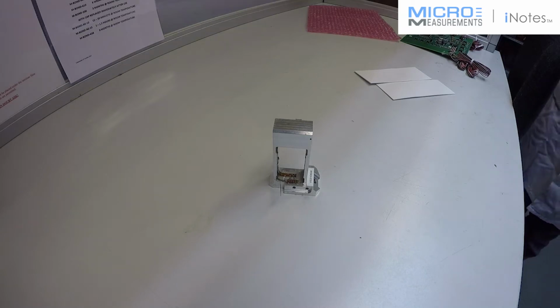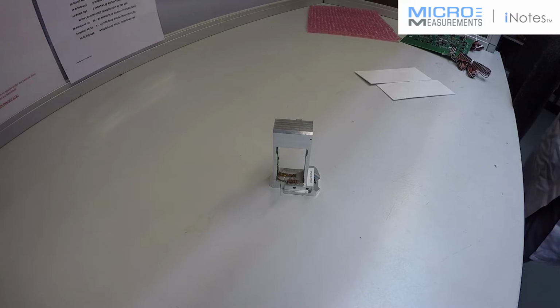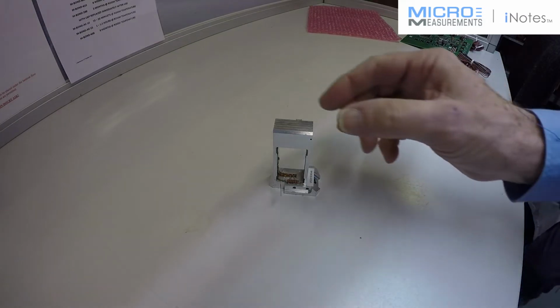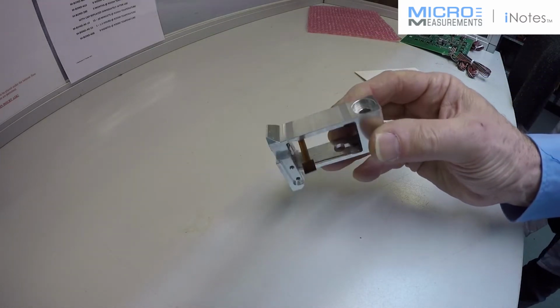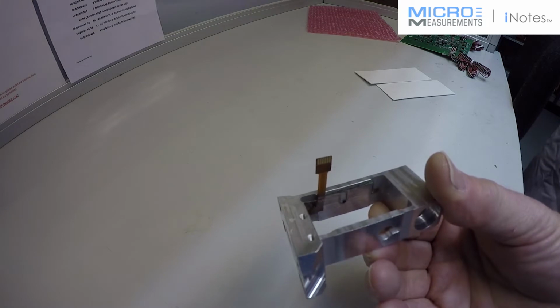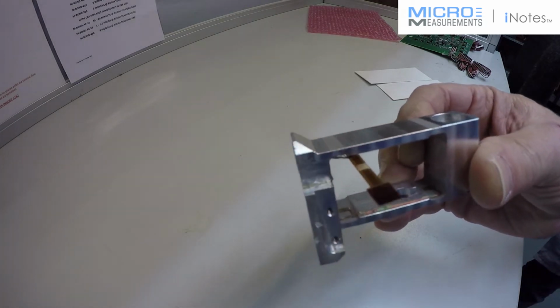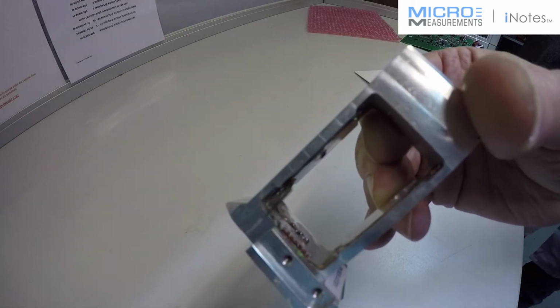This looks like a very interesting component here, Dave. What's happening here then? It's a binocular load cell. We manufacture quite a number of these in various sizes for various loads. It's got 4 gauges which are mounted in the reduced section, giving us a binocular load cell measuring a bending load. In addition, there's a flexible PCB circuit for connection into the electronics that it's finally used in.